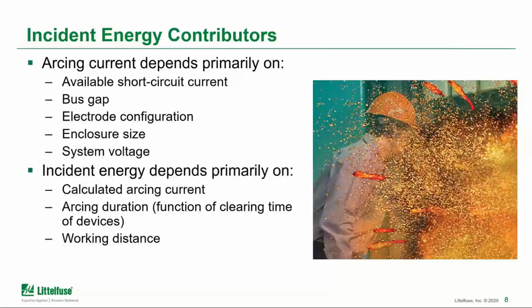So in general, a bigger gap will give you more impedance, which could mean less current, if all the other variables are constant. And IEEE 1584, the standard we'll talk about in a little bit, does have some guidelines for those bus gap distances, tables with default values. And the electrode configuration is also something that has a significant effect. So we'll review that as well.